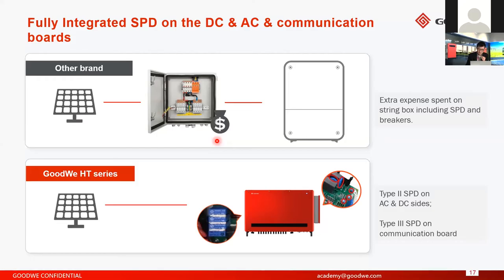So if the inverter doesn't have the type 2 SPD on the DC side, you must buy an external string box. So that's also an additional cost for the installers and for the users, to buy the string box on the DC side. So that's a cost for the customer also. But if you buy an inverter like GoodWe, which already has the type 2 SPD on each string of the DC side, you don't need to buy the string box between the panels and the inverter. So you can save some investment on the DC side.